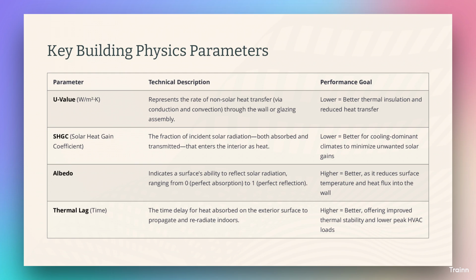Key building physics parameters. Parameter: U value, W/m²K. Technical description: represents the rate of non-solar heat transfer, via conduction and convection, through the wall or glazing assembly. Performance goal: lower equals better thermal insulation and reduced heat transfer. Parameter: SHGC, solar heat gain coefficient. Technical description: the fraction of incident solar radiation, both absorbed and transmitted, that enters the interior as heat. Performance goal: lower equals better for cooling dominant climates to minimize unwanted solar gains.